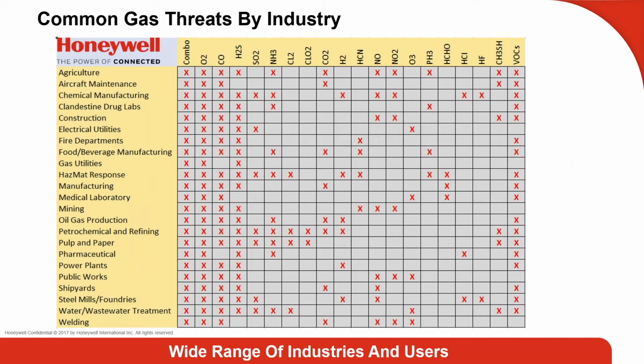This is a slide to look at, where we're looking at different industries and the common threats in each. It's not exclusive, and in some cases where there's not a checkbox, that application may still have that hazard. But the takeaway is you can see these four gases on the right, combustible, oxygen, carbon monoxide, and hydrogen sulfide, heavily populated on the left-hand side. That's your standard four-gas configuration that meets the needs of most of these industries. Then you see sparsely populated gases: sulfur dioxide, ammonia, chlorine dioxide, carbon dioxide. Sometimes people confuse CO with CO2 and vice versa. Also hydrogen cyanide, nitric oxide, nitrogen dioxide, ozone, phosphine in the fumigation industry, formaldehyde, hydrogen chloride, hydrogen fluoride, and all the VOCs you see here on the right.